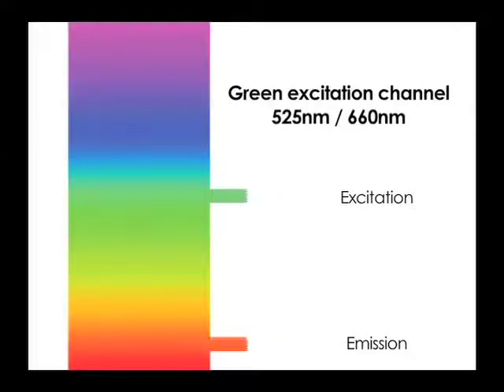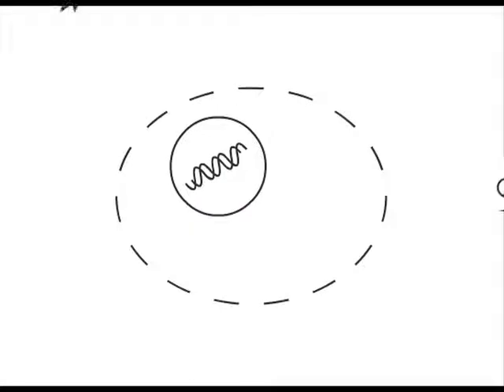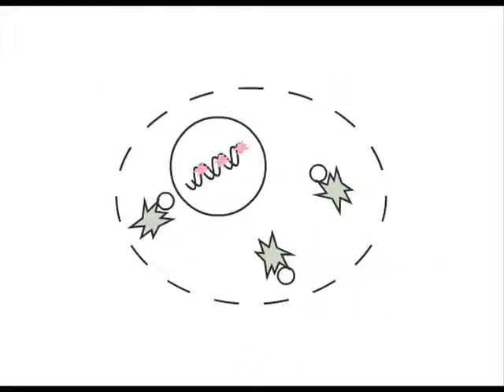Channel 2 of the cellometer has green excitation to detect red emission. For a dead cell, PI enters through the damaged cell membrane and binds to its DNA, producing very strong red fluorescence.